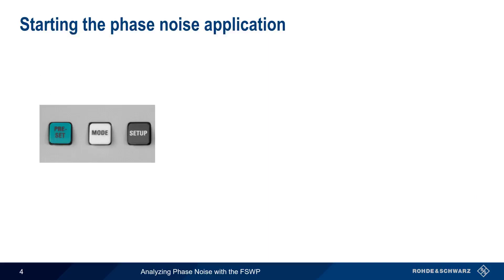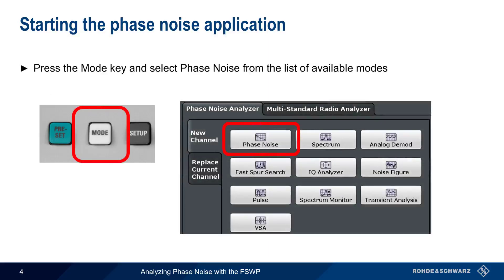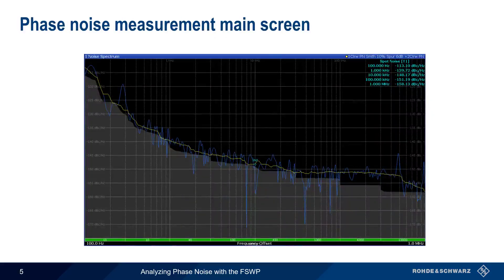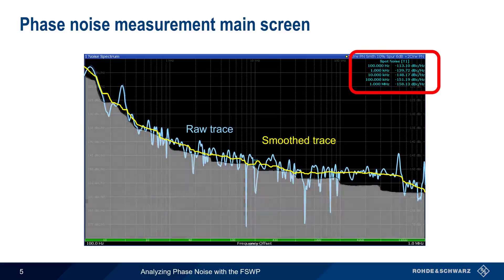To start the phase noise application on the FSWP, simply press the Mode key and then select Phase Noise from the list of available modes. This is the main phase noise measurement screen. In most cases, the source signal will be automatically detected and measured. By default, phase noise results are given as both raw and smooth traces of the single-sideband phase noise, and are also shown as numeric spot noise values. If cross-correlation is used, the gray area beneath the trace shows the cross-correlation gain.